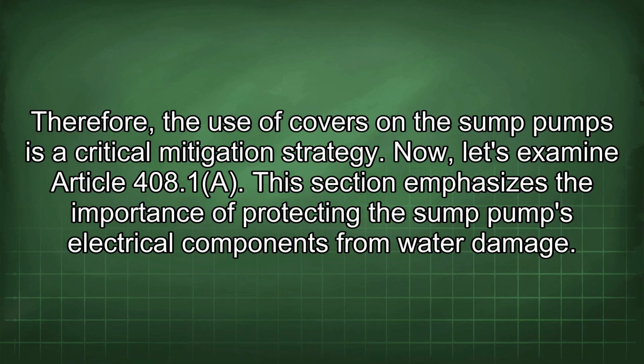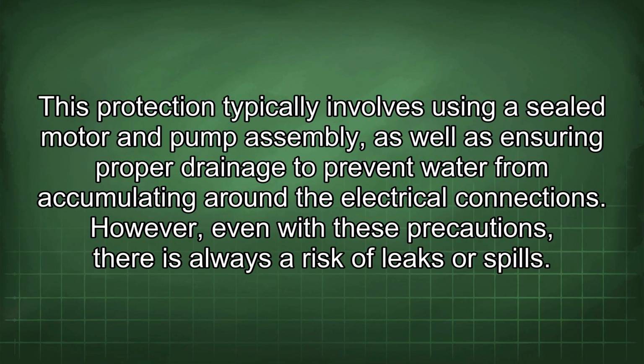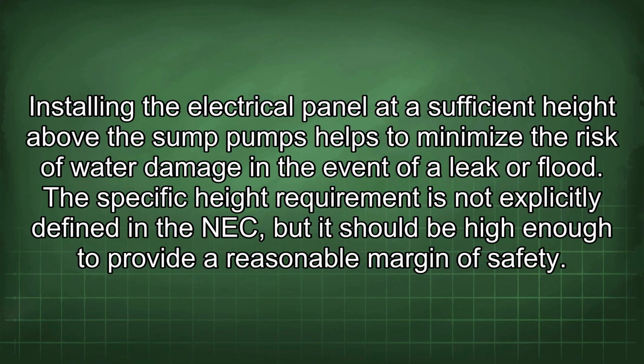Now, let's examine Article 408.1a. This section emphasizes the importance of protecting the sump pump's electrical components from water damage. This protection typically involves using a sealed motor and pump assembly, as well as ensuring proper drainage to prevent water from accumulating around the electrical connections. However, even with these precautions, there is always a risk of leaks or spills. Installing the electrical panel at a sufficient height above the sump pumps helps to minimize the risk of water damage in the event of a leak or flood.